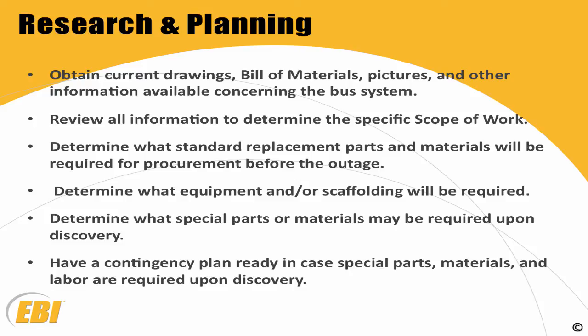Then you need to determine what standard replacement parts you need to make sure that you have before the outage. Determine what kind of equipment or scaffolding will be required. Then you need to determine what special parts or materials may be required upon discovery. And you need to have a contingency plan in case problems like that come up.